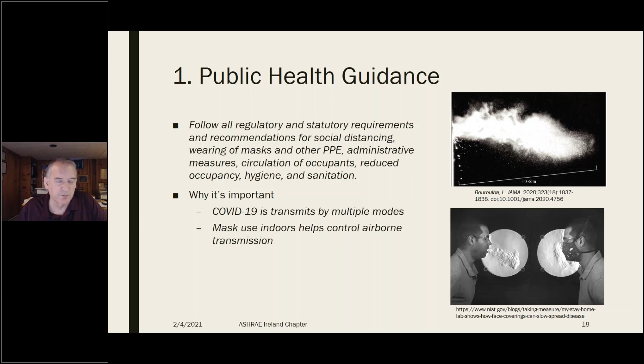COVID-19 is transmitted by multiple different modes, and HVAC only affects one of them, airborne. So we still need to be doing things that will help control close contact and, in case it exists, fomite transmission. And the other reason is that mask use is very significant in terms of its ability to reduce the risk of airborne transmission, because it blocks jets that might be produced by coughs and sneezes. You can see the well-known by now image of the sneeze traveling 8 meters away from the source in the upper figure. And in the lower one, you can see that wearing even a cloth mask stops that from happening, and also will substantially reduce the amount of infectious material that's put into the air, and will provide some protection to uninfected wearers. So this is really, really important even for airborne transmission.